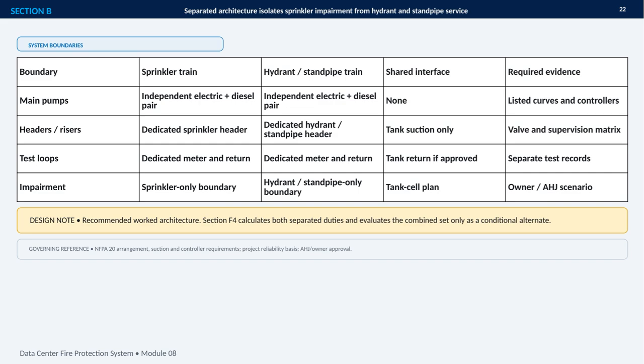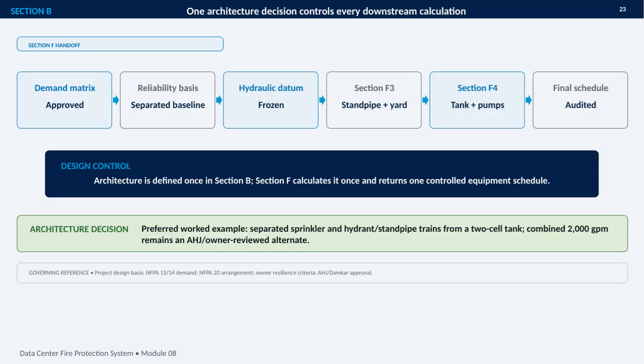The hydrant and standpipe train follows the same pattern, but remains hydraulically separate. The tank suction is the only shared interface identified here, and even that connection is subject to the approved tank cell plan. This separation also creates distinct impairment boundaries. Testing, valve supervision, and records need to demonstrate which train is affected, while the owner and authority having jurisdiction review the impairment scenarios. The recommended architecture is to calculate the two duties separately, evaluating a combined set only as a conditional alternate. Final design evidence must address NFPA 20 requirements, project reliability criteria, and the required owner or AHJ approvals. This slide establishes the design control logic for the handoff from Section B to Section F.